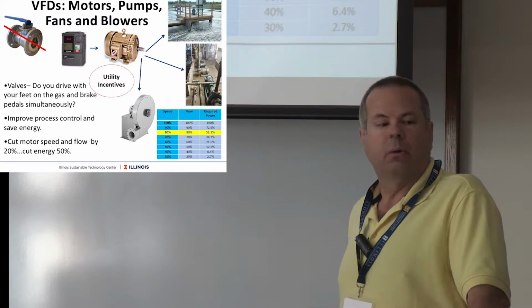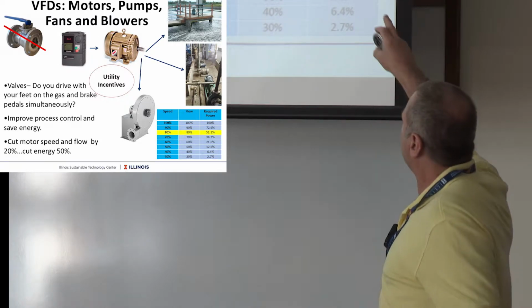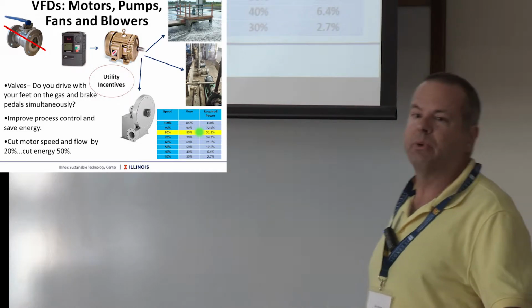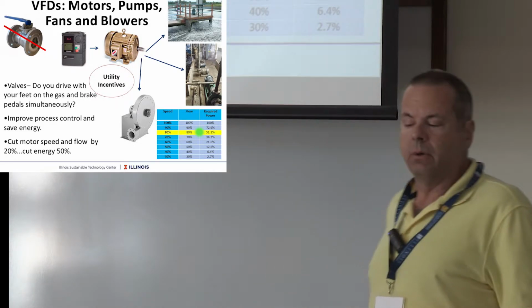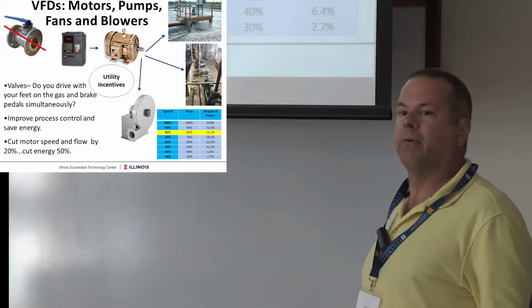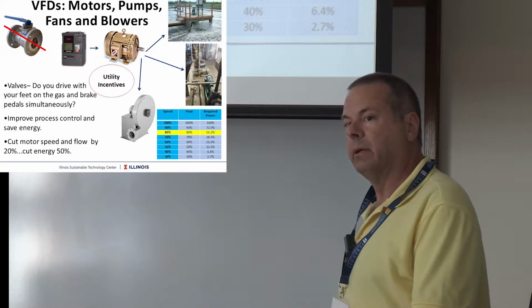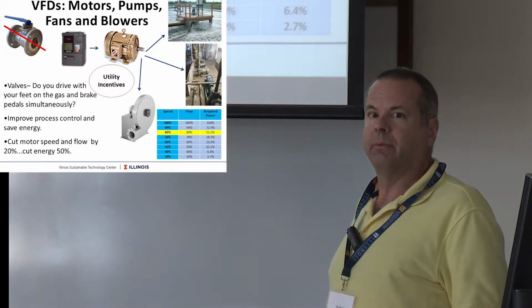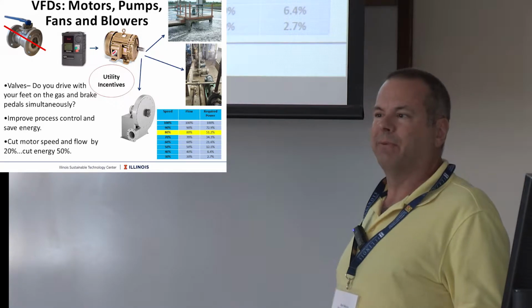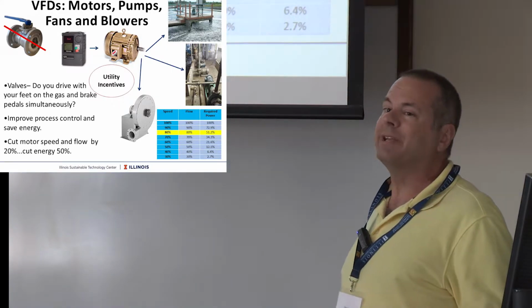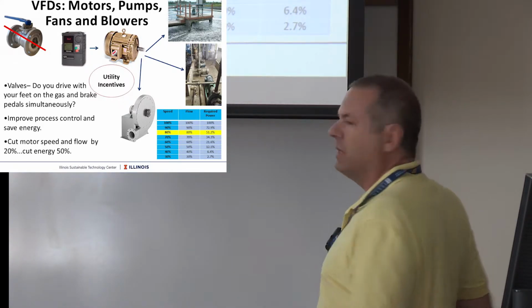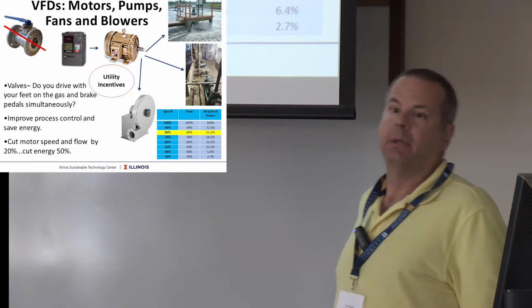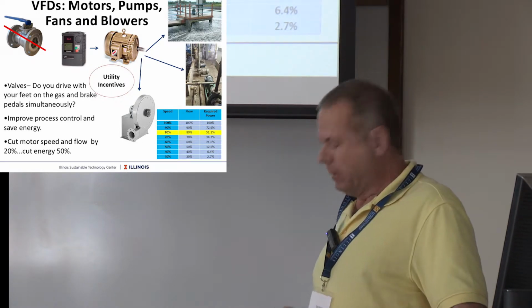A 20% reduction of flow, if you can see that right here, will yield almost a 50% energy savings. So it's not unusual for us to see valves 50% back. A 50% reduction of flow will yield you almost an 87% reduction in power. So that's huge.